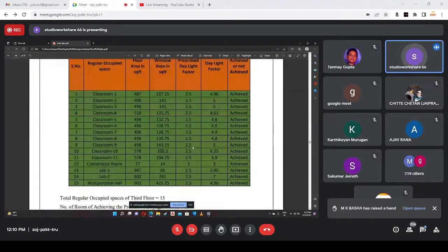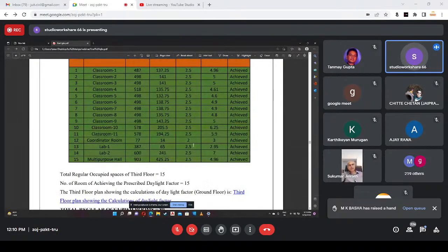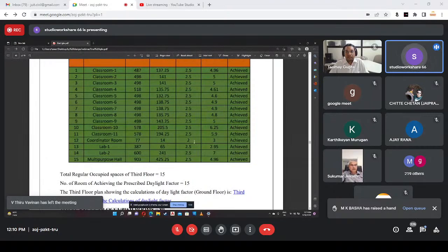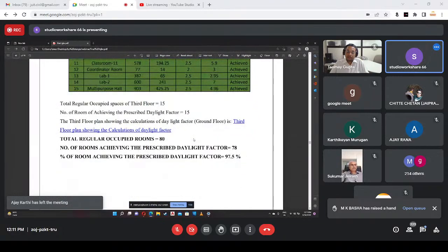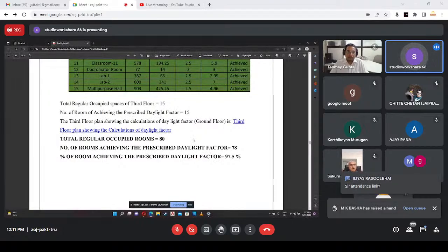The daylight factor must be carefully balanced with the amount of heat entering the rooms. In our case, the selection of glass was done carefully so that you get the required amount of light without too much heat entering the building, which would add to the air conditioning load. For all the facades, we selected the glass appropriately to balance light and heat entering the classrooms. We did a simulation and procured solar control glass accordingly.